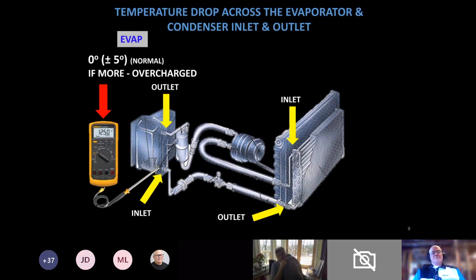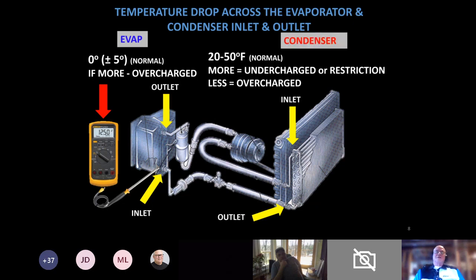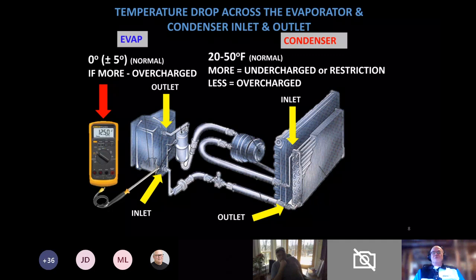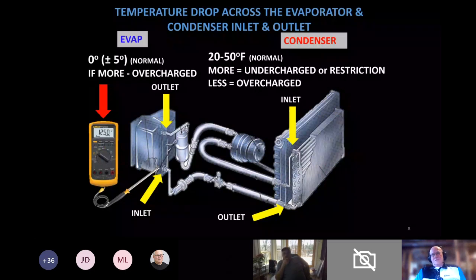If you have an evaporator, you want very little temperature change between the inlet and outlet, 0 or plus or minus 5 degrees. That's normal. If it's more than that, it's probably overcharged. On the condenser, you want about a 20 to 50 degree difference between the inlet and outlet. More, it's undercharged or is restricted, either refrigerant restricted or airflow restriction. Less is overcharged. This is a silver bullet. It's a ballpark, but it's a quick and easy way of determining the state of charge and efficiency of your system.